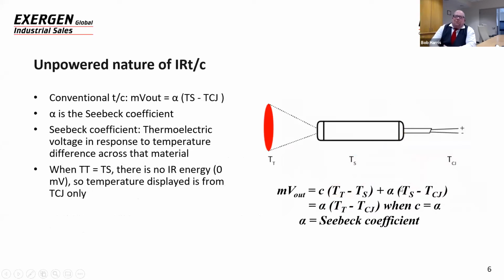Now, back in the early 90s, Exergen listened to the customers in the industry, and what the industrial world needed was an infrared sensor, not a pyrometer, but an infrared sensor that could be a drop-in replacement for a thermocouple. So Dr. Frank Pompey invented the product called the IRTC, which stands for infrared thermocouple. The whole idea of the IRTC was to have a drop-in replacement for conventional thermocouples. So we calibrate an IRTC so that the millivolt output matches that of a conventional thermocouple.